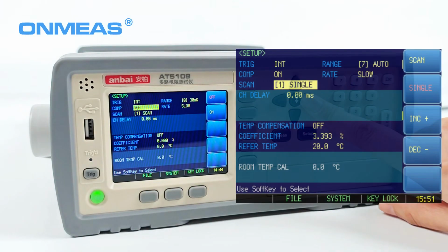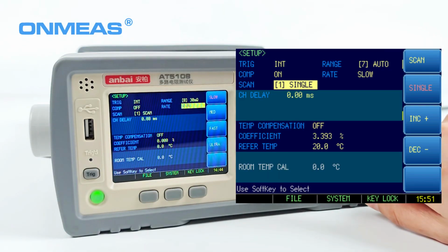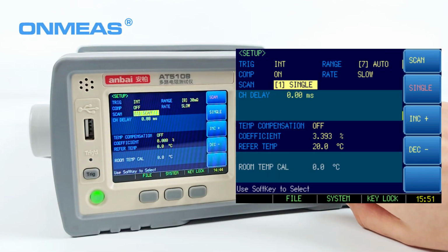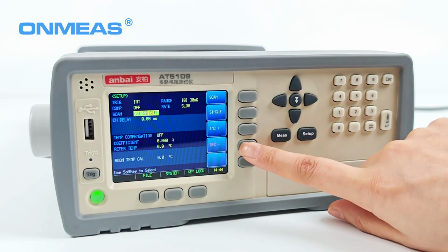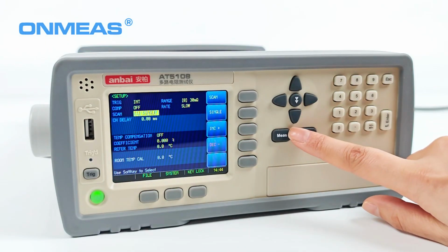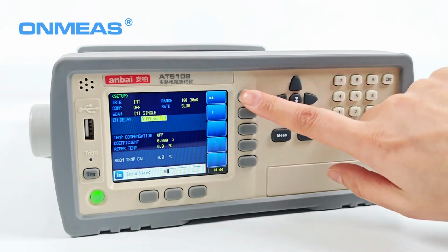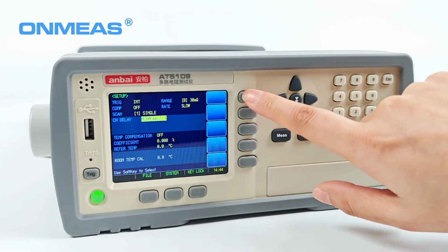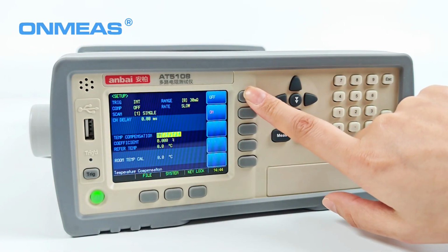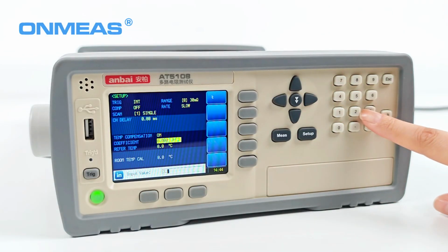The instrument offers 4 different testing speeds. The slower the speed, the more accurate and stable the test results will be. Scanning can be set to single channel or full channel. For single channel, the specific channel can be selected by increasing or decreasing. All the values can be directly entered using the numeric keypad.